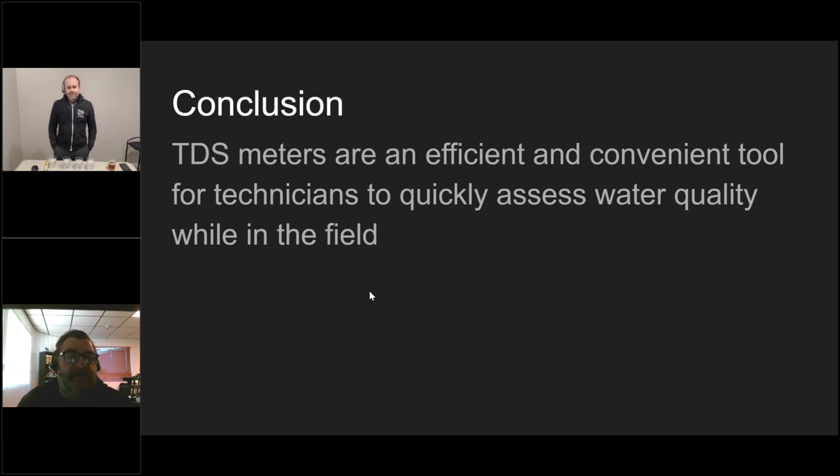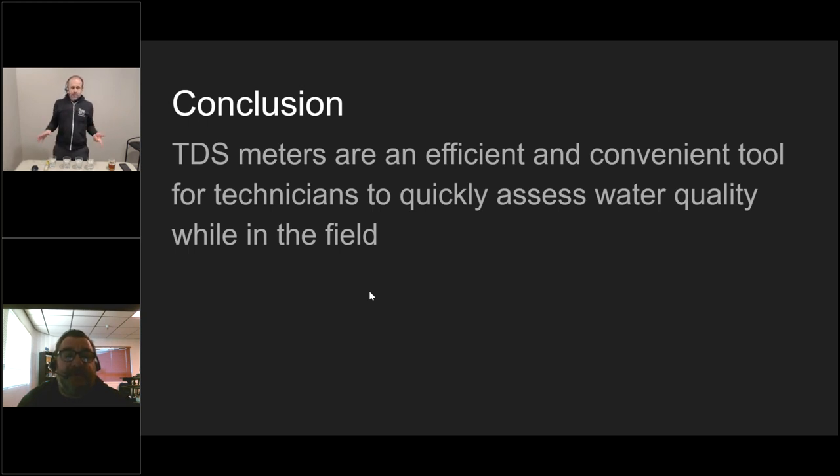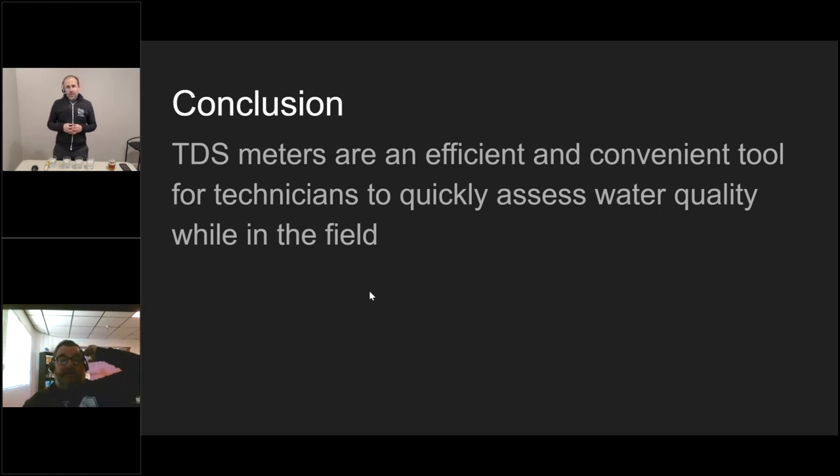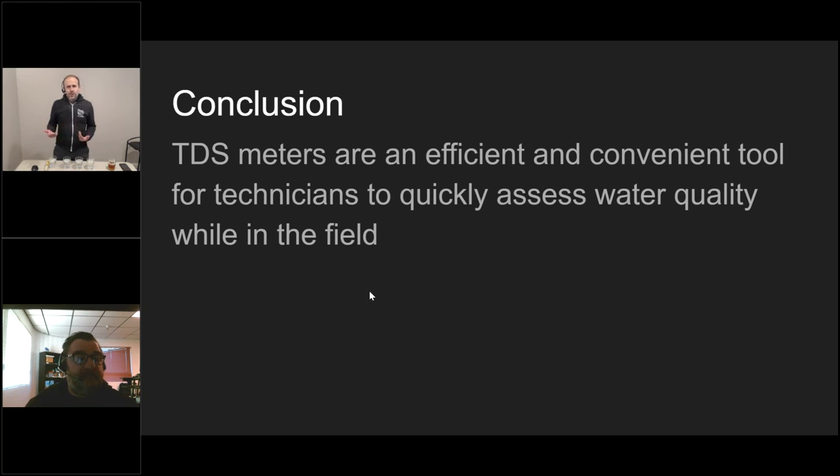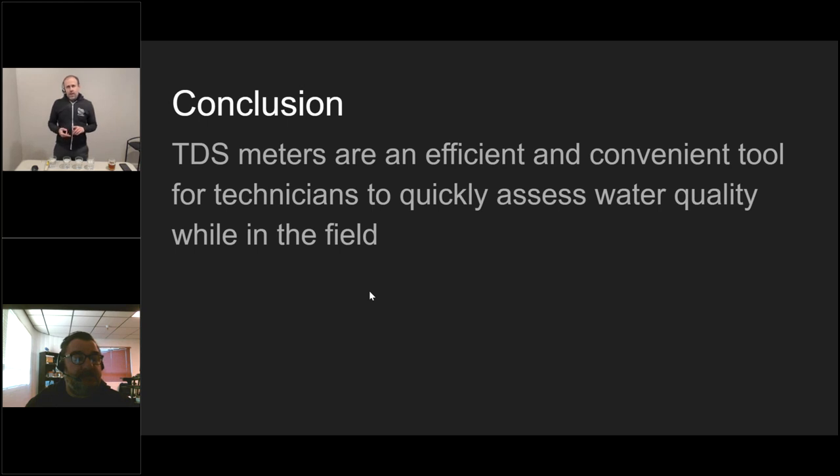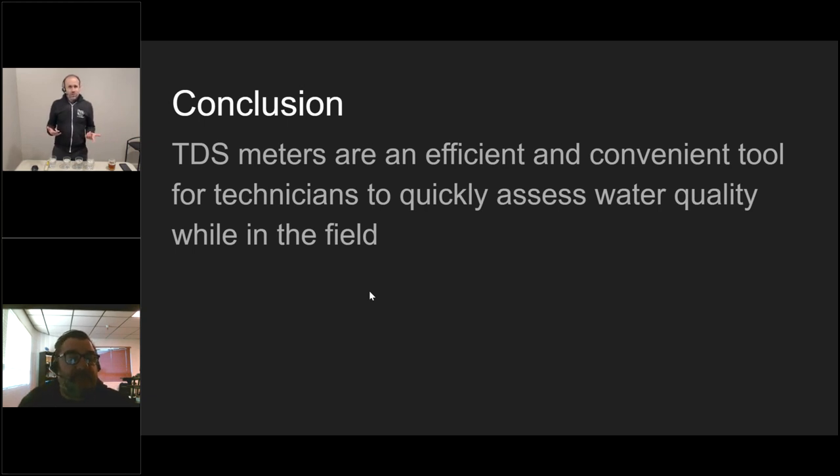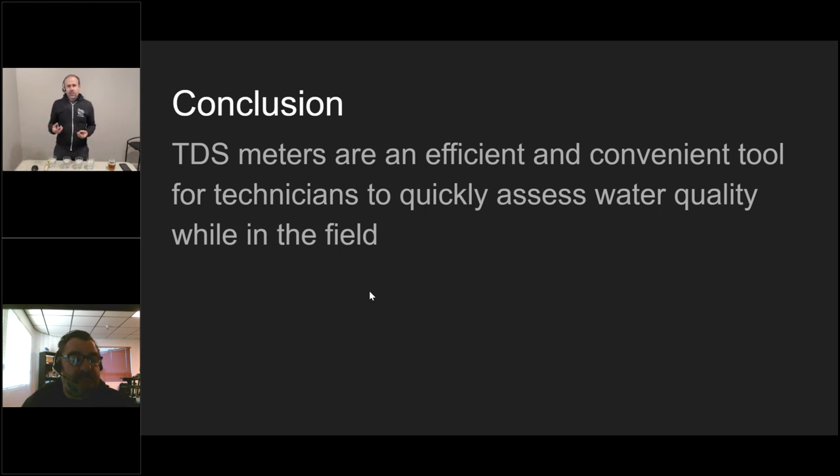So the TDS kit and the Hach kit need to be part of your standard carry, correct? Yeah, you should do it every service, ideally. It doesn't really take that long to go through those several parameters. I don't test for chlorine or chloramines, but I do test generally for hardness. I will test for alkalinity and I will test for chloride. Those are the three. Iron, if you've got an iron problem, you don't need to test for it. It's going to start staining things. You'll see some blackishness around drains and things like that.